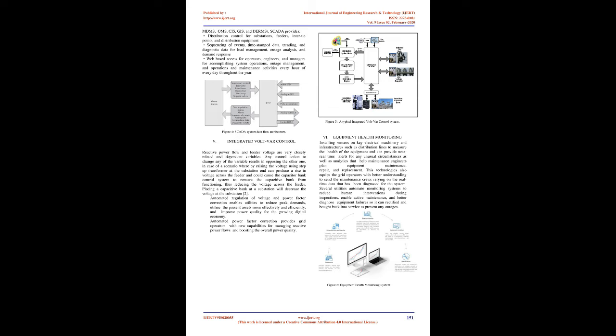SCADA systems process operational data from the field and display status on control center operator screens or the HMI, human-machine interface. Abnormal conditions trigger display alarms, which are then acted on by the grid operators, who can issue operator commands. DMS can also automatically issue SCADA commands. Locating faults using SCADA allows utilities to isolate and repair faults and restore service quickly, thereby increasing system resilience.